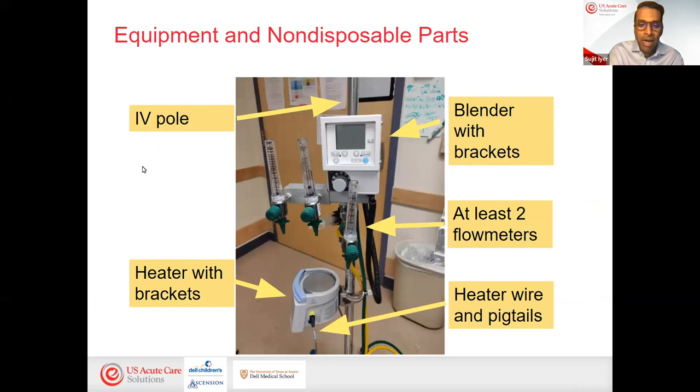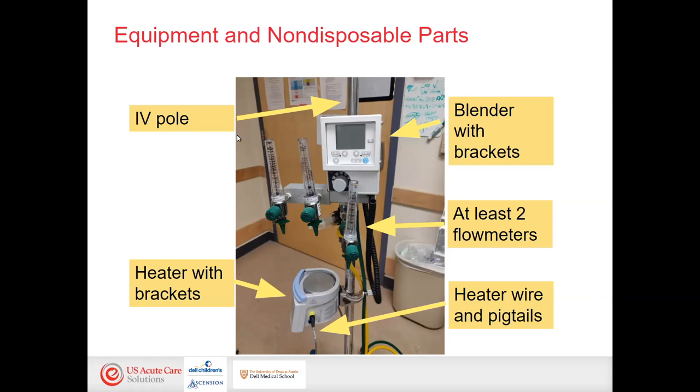Here we'll walk through how to set up high flow nasal cannula through one system. Your own equipment may vary, and your local respiratory therapist should know how to set this up. At Dell Children's we use the OptiFlow Junior 2, but all devices have similar mechanisms. You'll have a IV pole, a blender to manipulate FiO2, at least two flow meters, heater brackets to hold the heater, and pigtails that connect to the circuit.